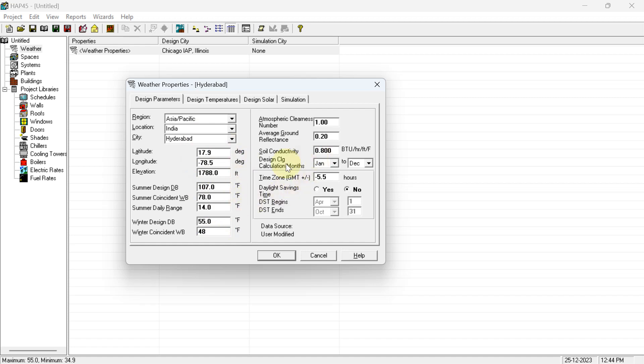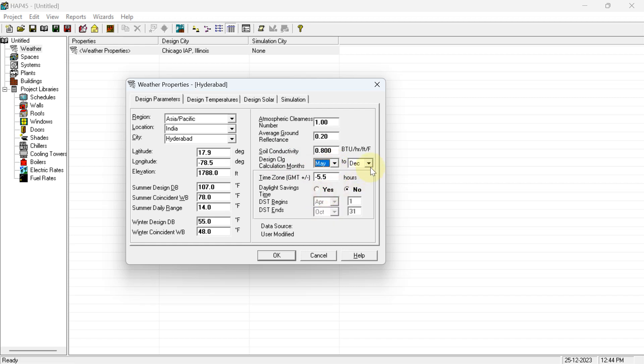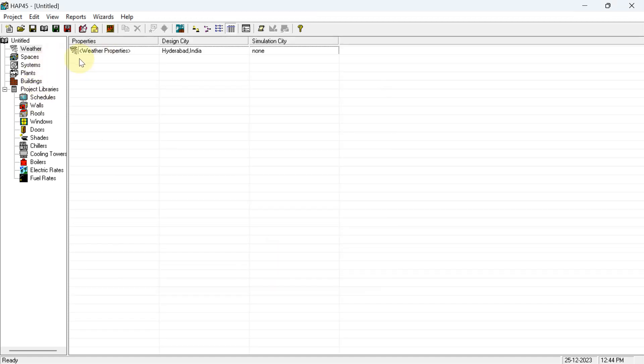The winter dry-bulb temperature is 55°F and the coincident wet-bulb is 48°F. Fill in all these details. For the design cooling calculation month, select the month you feel is hottest — I am selecting July. Finally, hit OK. The weather properties are now done.